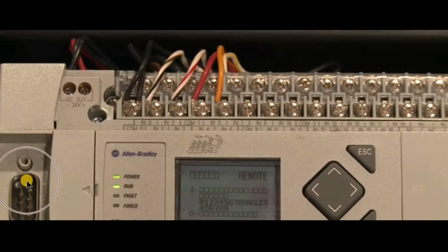Along with that, on your left side you will get one communication port, that is nothing but the RS232. By using that communication port, we can download the program which we have designed in the software. Now here you can observe some buttons like the upward key, downward key, right, and forward and reverse keys. Along with that, here you can see the escape button, and below that the OK button. Before setting the IP address, make sure you press the escape button, meaning you go out from the last setting and you can provide a new setting to your MicroLogix PLC.